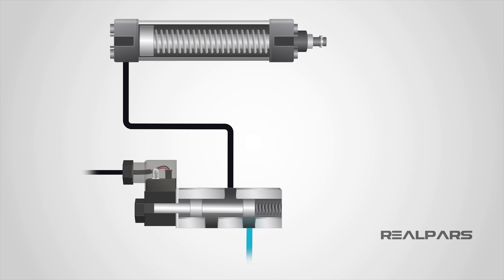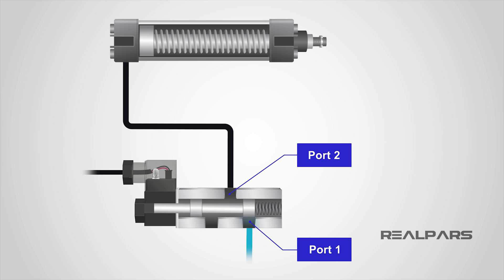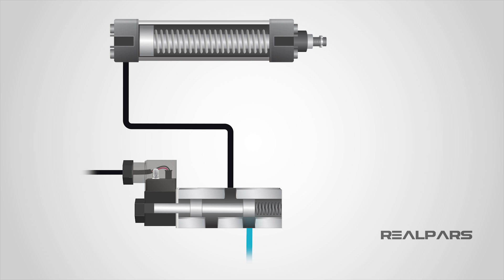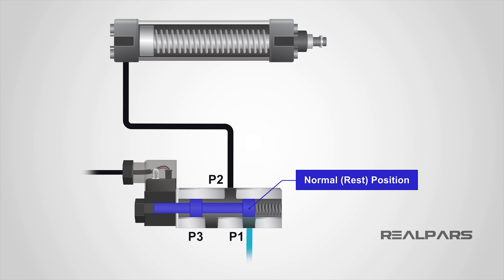Imagine the example of extending a pneumatic cylinder using a spool valve. The pneumatic air supply is connected to the inlet port 1. Port 2 is connected to the pneumatic cylinder extend connection. Port 3 is unconnected, as it is the exhaust port. In the normal state, without the actuator being operated, nothing will happen, as the spool is physically blocking the airflow at port 1, and the cylinder is retracted because ports 2 and 3 are connected due to the spool position. Any air already within the system would escape to the atmosphere through the exhaust port. Let's consider this the normal or rest position.